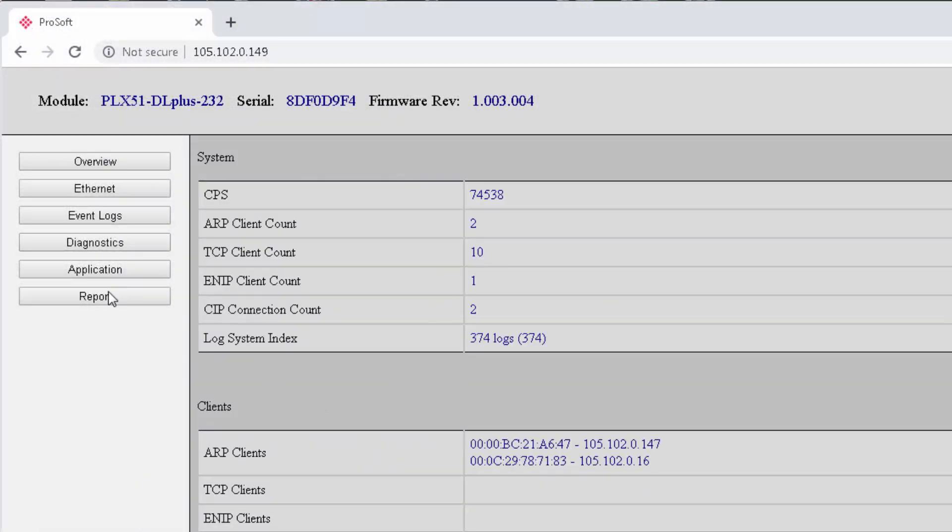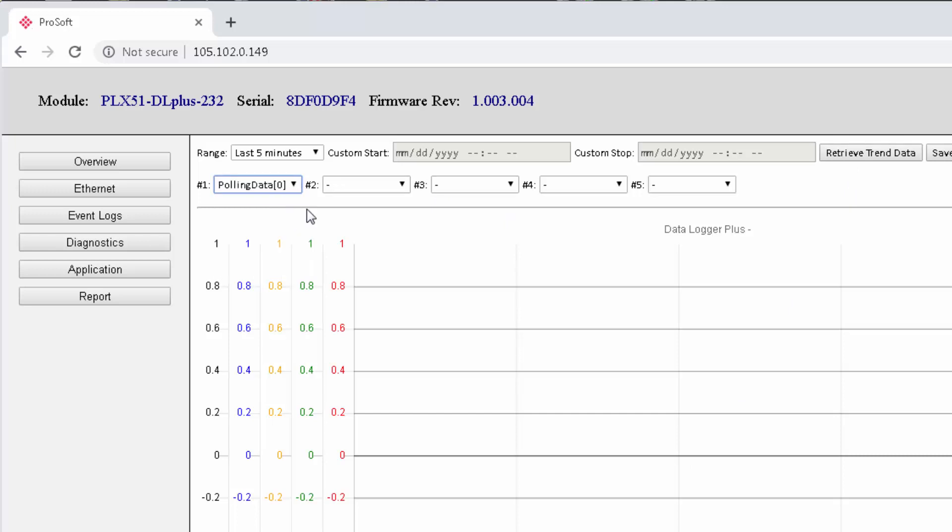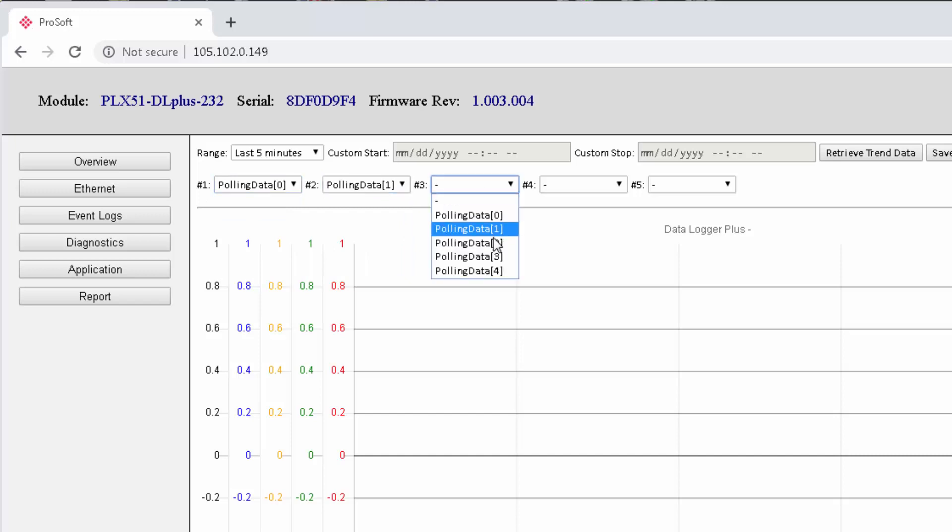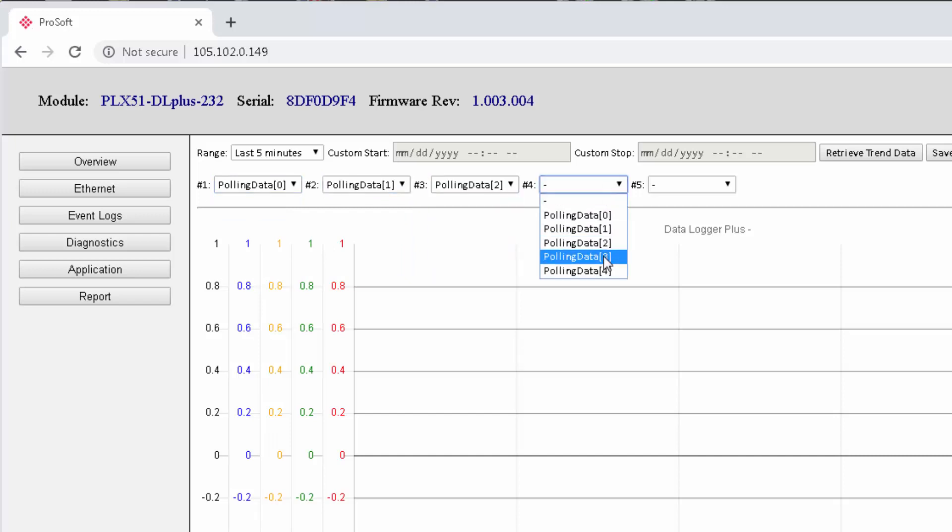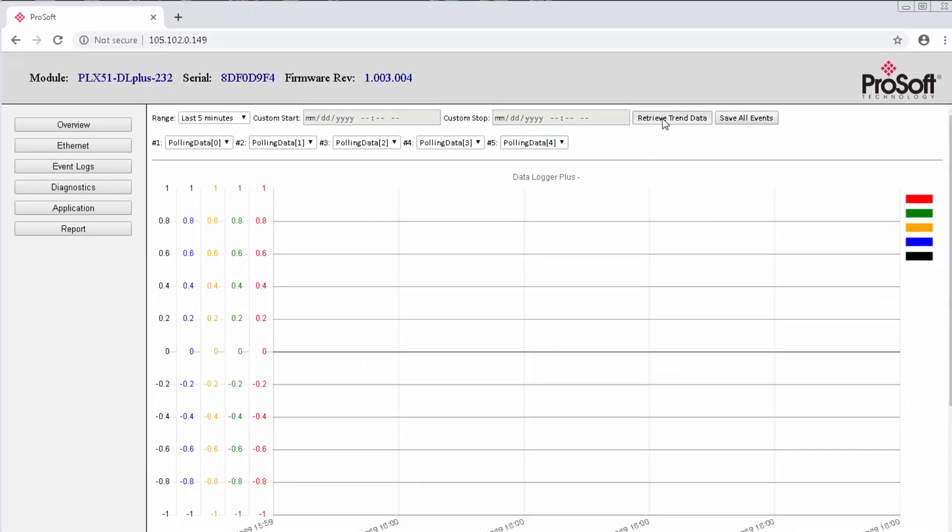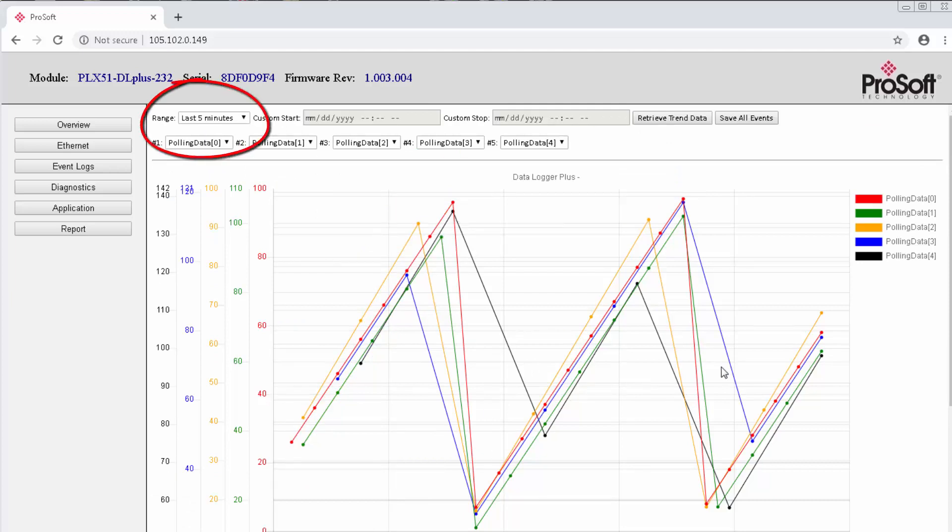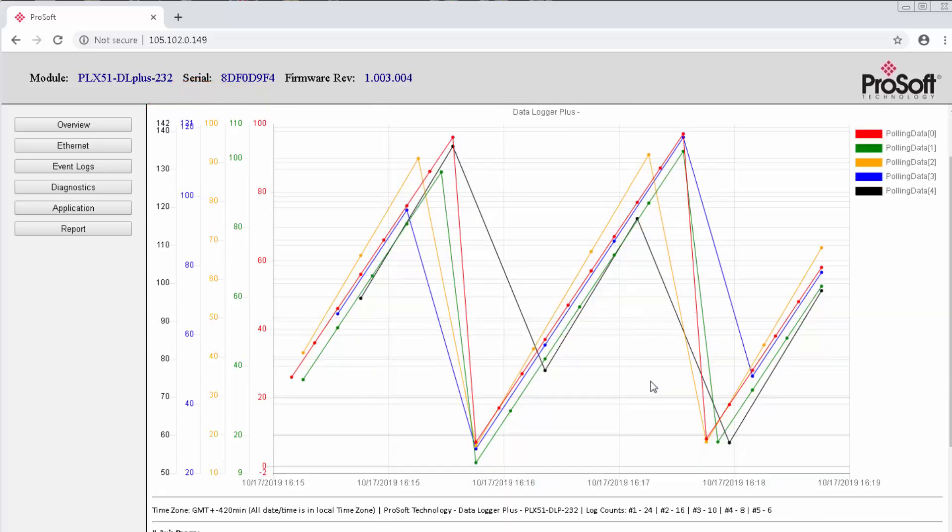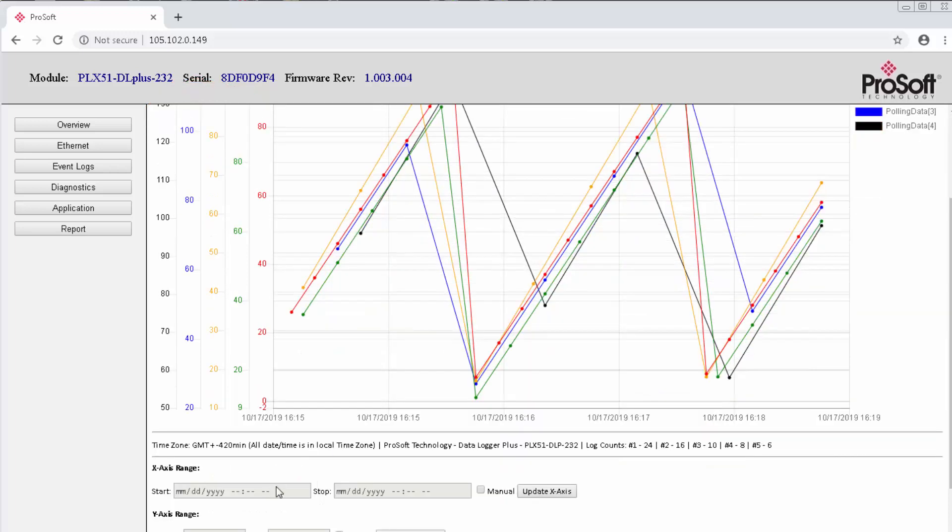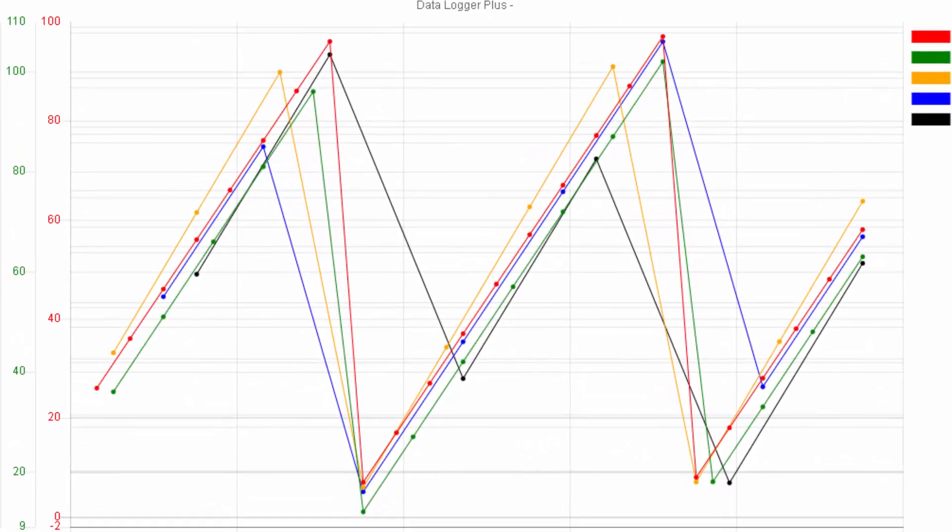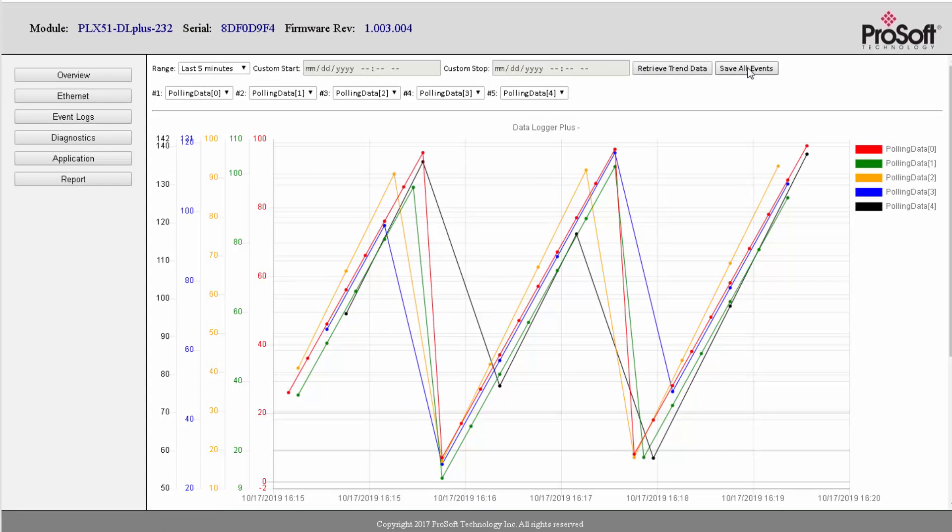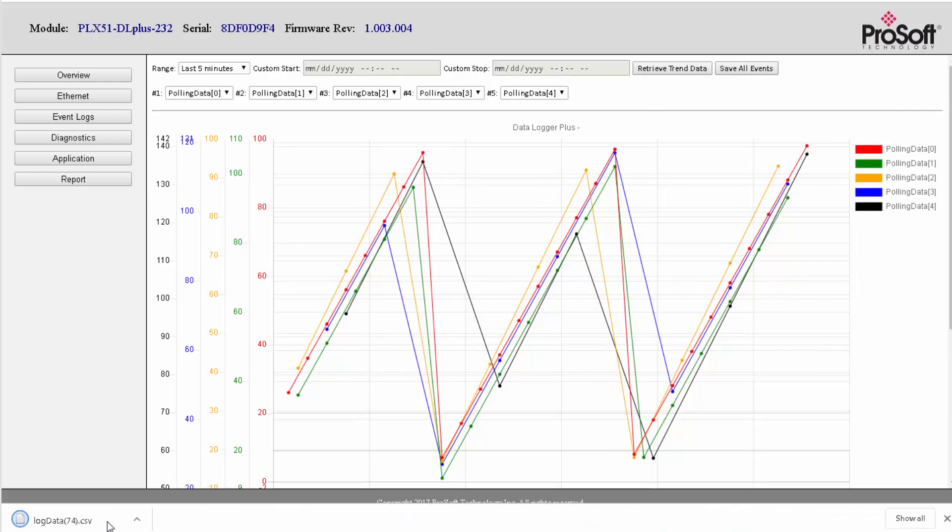We'll go down to Report, where we can grab data logs for up to five tags at a time and generate a graphic report for them. So I'll use the drop-down menus at the top to select each of my five tags. Each one will be assigned a color. Just click Retrieve Trend Data, and you should get a graph something like this. Now, if not, it might be because you need to wait for whatever time range you have selected to elapse before a trend can be recorded. This is not a live feed, it's just a snapshot of the past few minutes' worth of log data. Each dot on this graph represents a data point at the time of capture, and from here you can see the value of each tag over time, as well as where logs are being recorded. You can also click the Save All Events button to generate a spreadsheet with all the values and times of log data for these tags.